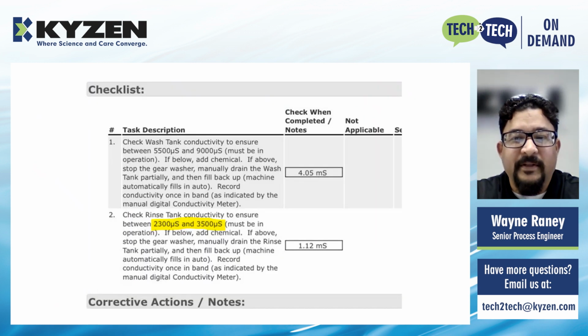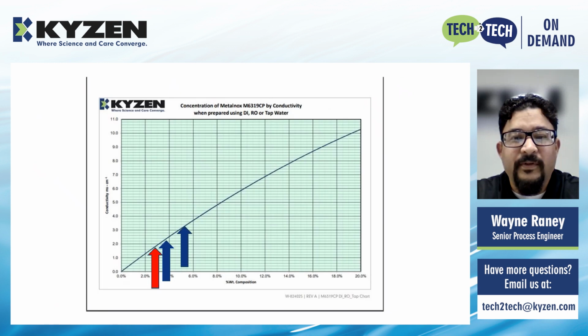But the rinse tank specification in their operating instructions is 2.3 millisiemens to 3.5 millisiemens. 2.3 to 3.5 is indicated by the blue arrows. Their 3% concentration spec is indicated by the red arrow. The operating instructions say it should fall between the two blue arrows. So in addition to changing the wash tank spec, the customer also changed the rinse tank spec as well. This was found during the visit.